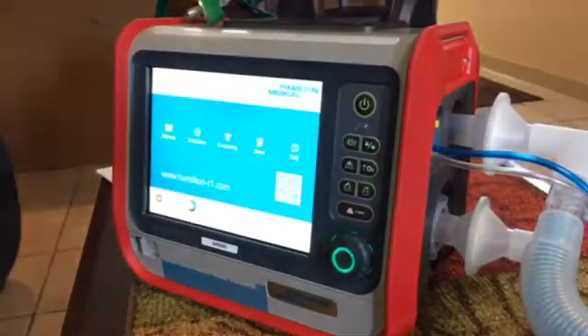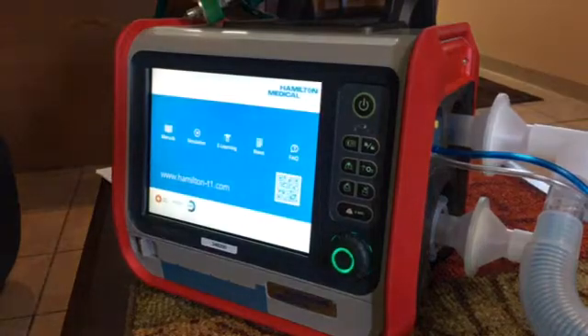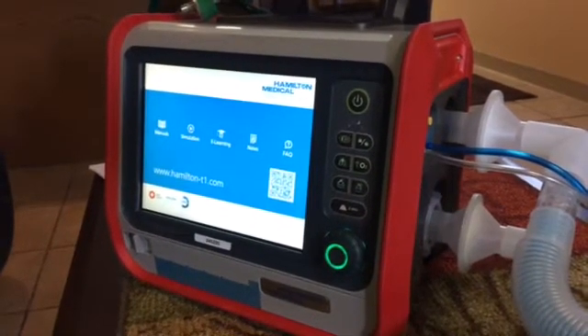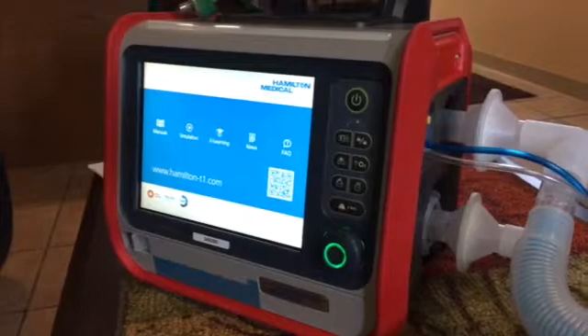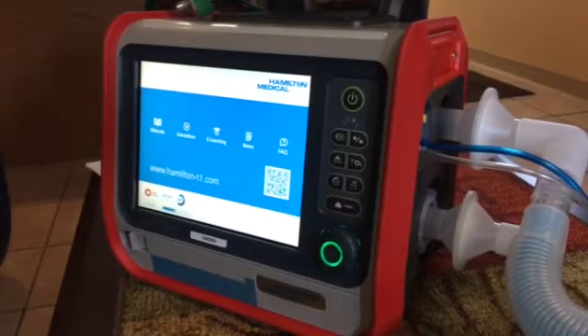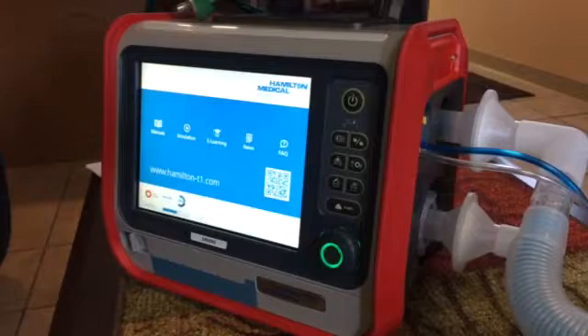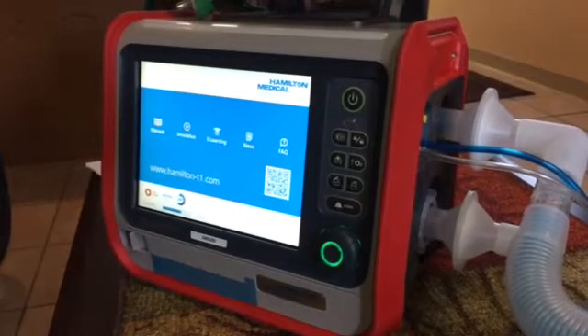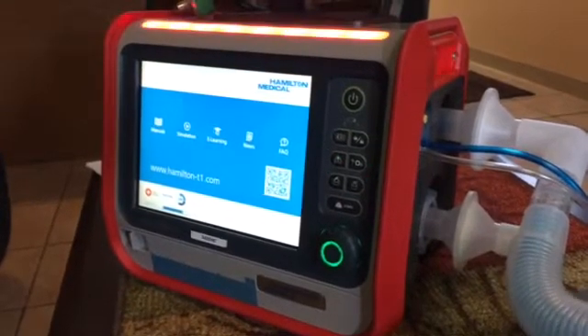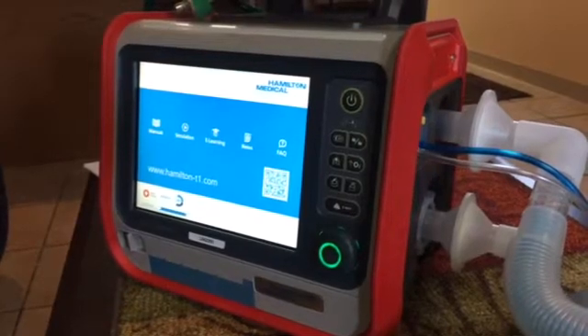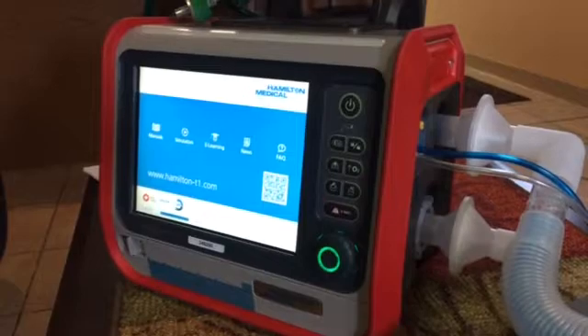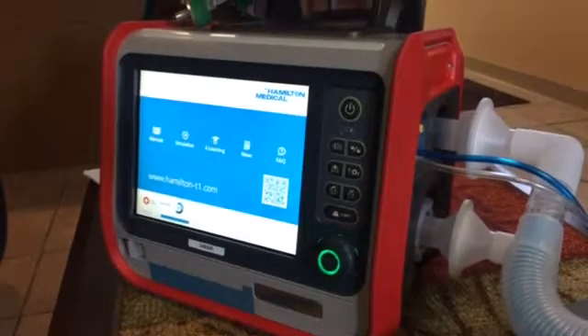When you first turn on the Hamilton ventilator after you've completed your circuit tests and all that stuff we talked about previously, it's going to light up to this screen. When the ventilator's done running through its cycle, it's going to come up to a home screen. What's cool about the home screen is we were able to choose three modes of ventilation to make it easier for you to choose what mode you need.